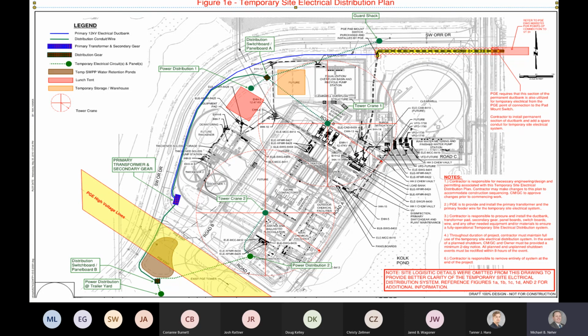Right now we've been working with PGE and we've done some single line, some one-line development. We've determined this is going to be a 2,000 amp system. The nearest power source PGE can provide is a 12 kV line, so we'll have to run a 12 kV temporary duct bank, bring it to a primary transformer, then step it down to 480 and distribute it from there out to panel boards and switchboards, then out to individual locations.